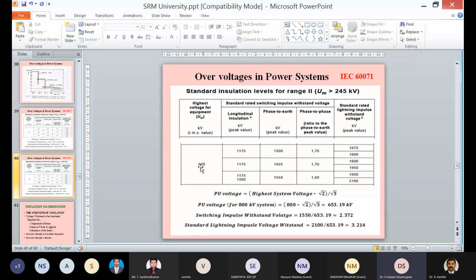I have taken an 800 kV system here. For an 800 kV system, the standard switching impulse withstand voltage is 1550 kV for phase to earth, and the standard lightning impulse voltage is 2100 kV. So again, the per unit value for an 800 kV system is 653.19 kV. The switching impulse level is 2.37 times the per unit value, whereas the standard lightning impulse level is 3.214 times the per unit value.